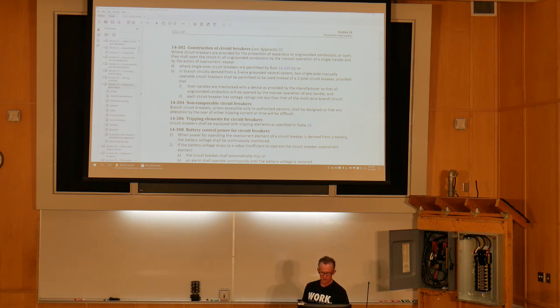Where circuit breakers are provided for the protection of apparatus or ungrounded conductors, or both, they shall open the circuit in all ungrounded conductors by manual operation of a single handle and by action of overcurrent, except where single pole circuit breakers are permitted by Rule 14-010B. That was the rule that if I had non-split receptacles or fixed lighting loads, I was allowed to use 2 single pole breakers. If I have a split receptacle, I have to use a double pole breaker. That's what 14-010 was about.